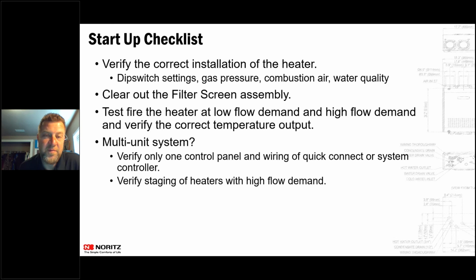I was actually on a call for about 40 minutes yesterday with a customer that was having an issue with getting the unit to fire and keep firing. I asked him the first time, is it a natural gas unit? And he said yes. And then we went through everything. And I'm like, are you sure it's a natural gas unit? And then he looked on the side and he said, no, they gave us a propane unit. So make sure that the gas type, number one, is correct for your install.